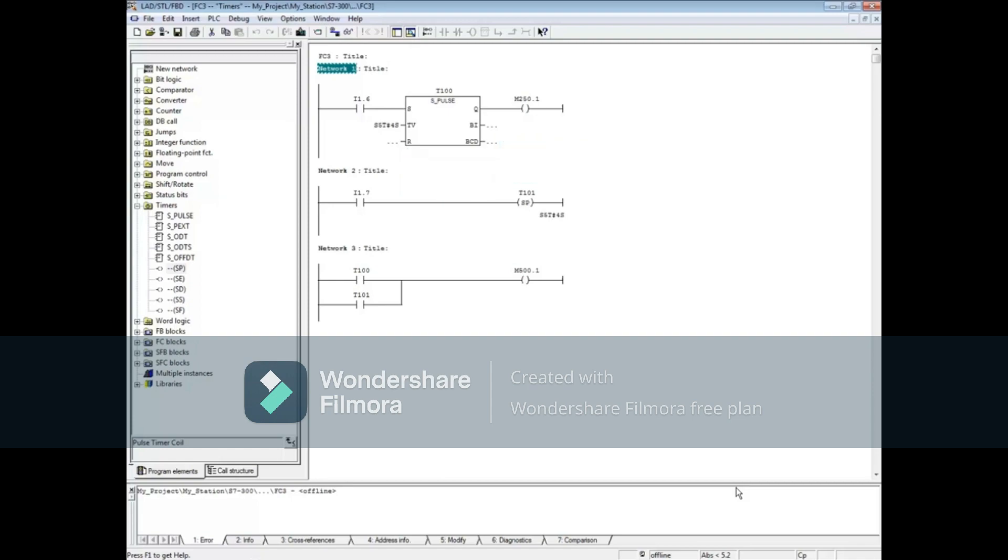The time format for all S7 timers is S5T pound sign followed by the hours, minutes, seconds, and milliseconds. The max time can be 2 hours, 46 minutes, and 30 seconds.